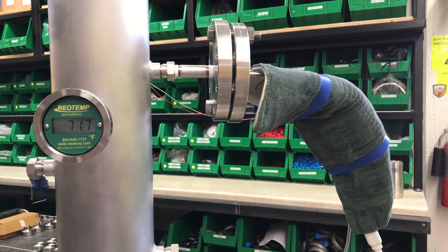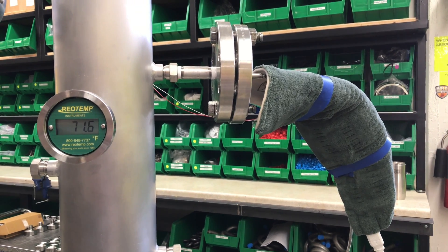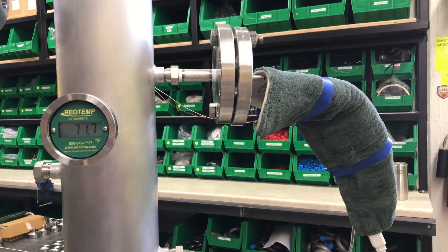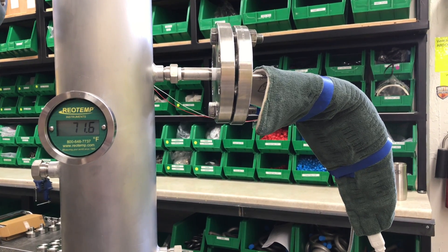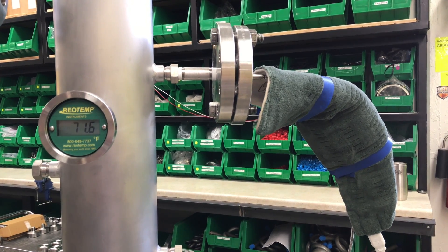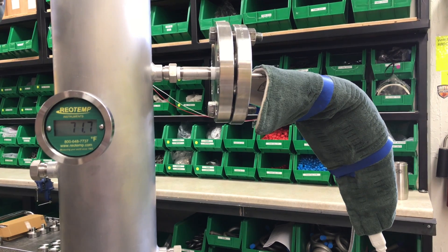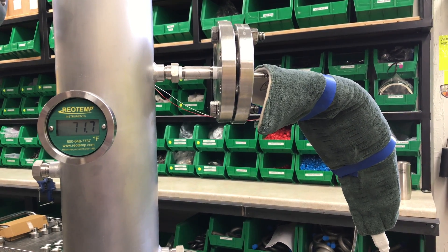In order to simulate an ambient temperature change, we have wrapped the low pressure side capillary in a heat blanket, in essence replicating the same effect as the sun rising and heating up the exposed capillary at the top of a tank. The column is empty and the transmitter is zeroed, so the only variable that will be changing is the temperature of the top 2 feet of capillary. Our starting ambient temperature is 71.6 degrees Fahrenheit.